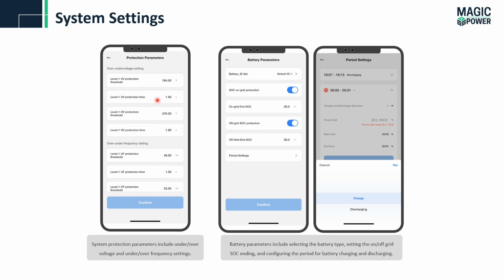For example, if it detects the protection threshold value, when it should be disconnected and how long it should take. For example, it's 1.6 seconds. Battery parameters for on-grid and off-grid SOC protection. So we choose 20% for both. It could be 10%, 15, or 20, 30, any value. For period setting, we choose the timing for charging and discharging our batteries. So again, it's for the peak and off-peak timings, like peak and valley prices.